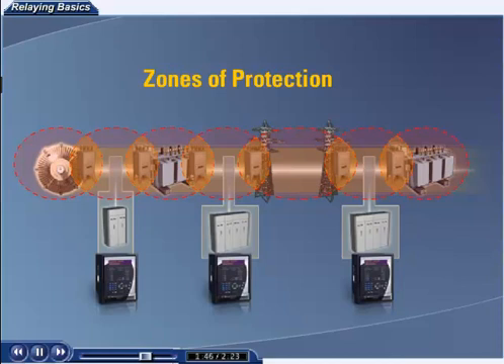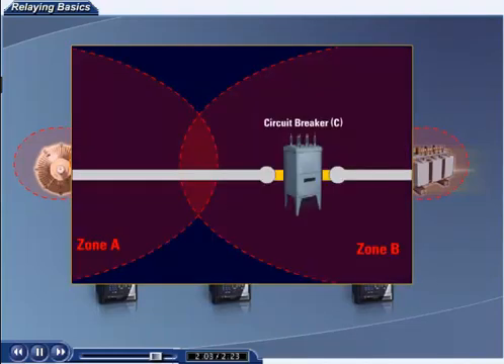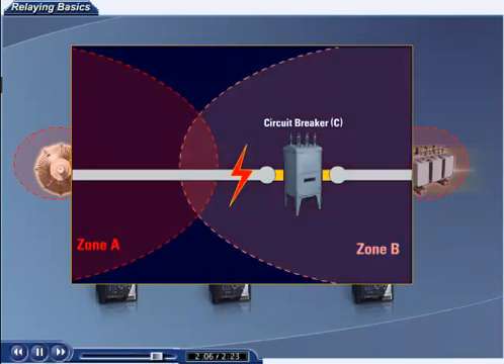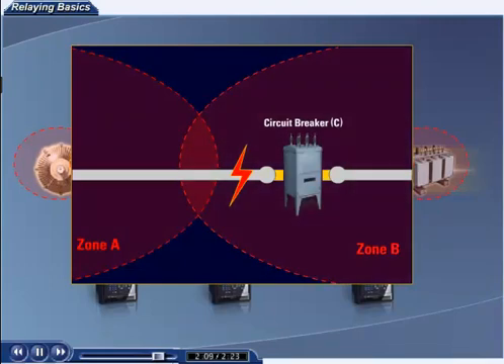If the zones of protection are set up such that overlap occurs on only one side of the breaker, the relaying equipment of the zone that overlaps the breaker must also be able to trip the breakers of the neighboring zone in order to completely disconnect faults in certain areas. This can be illustrated in the following example. For a fault located as shown, the circuit breakers of Zone B will trip, but because the fault is outside Zone A, the relaying equipment of Zone B will need to send a trip signal to the breaker in Zone A. A potential drawback of this is that the breaker in Zone A will be tripped unnecessarily for faults occurring in Zone B to the right of breaker C.